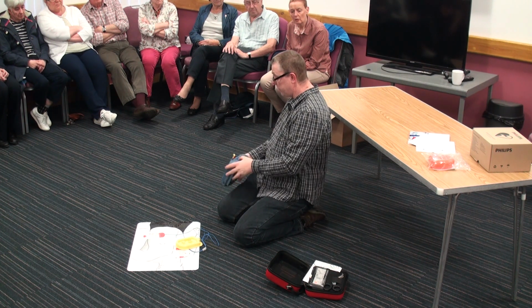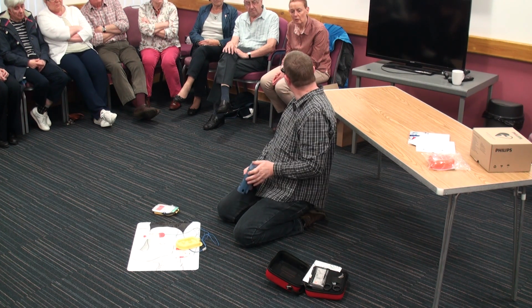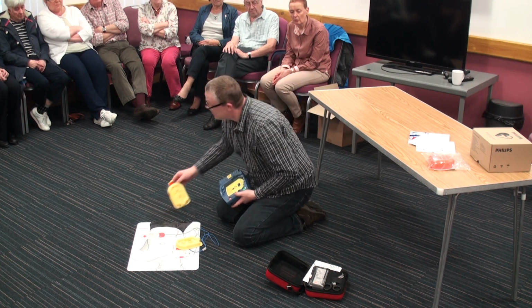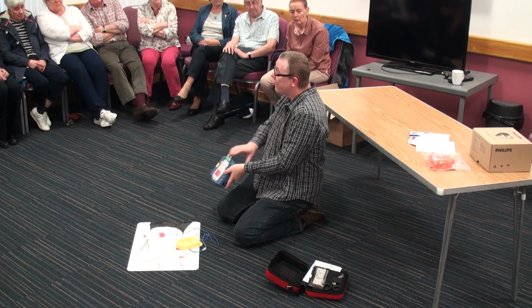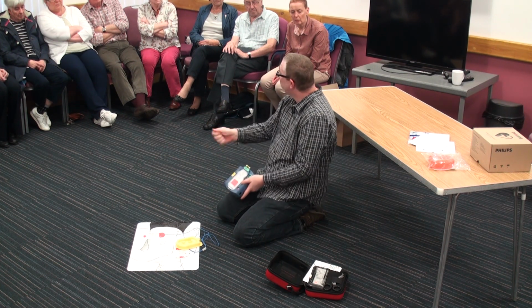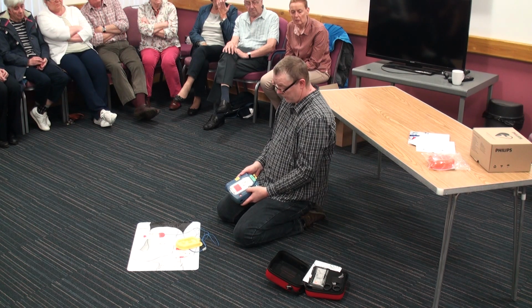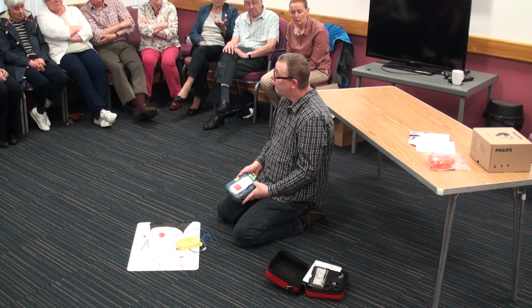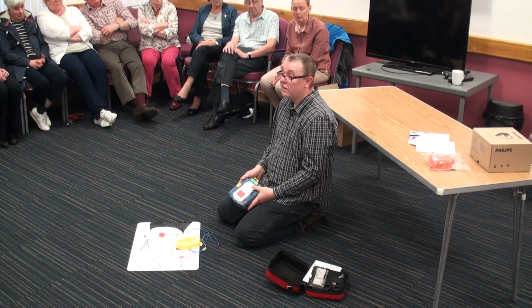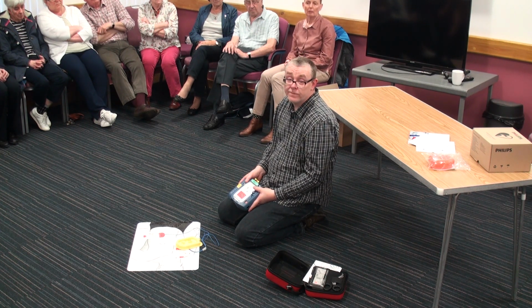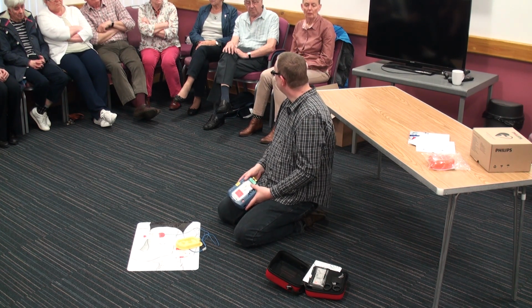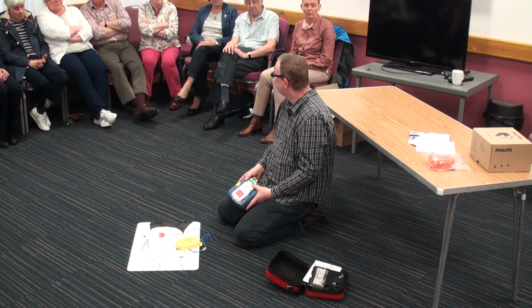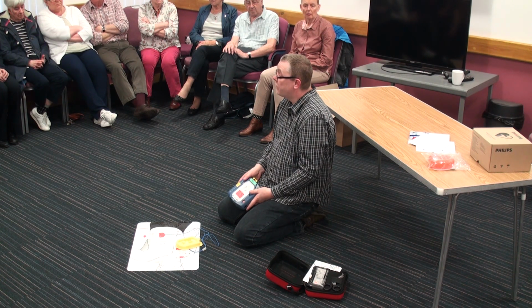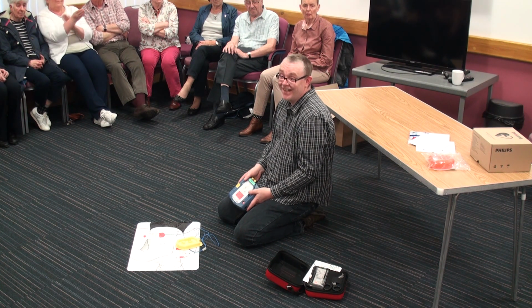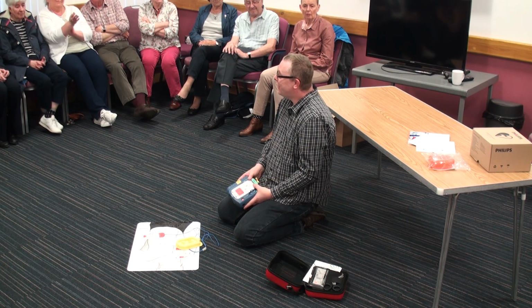Press the flashing blue button to insert the pads cartridge. I grab the child pads, set them in at the bottom, click them in at the top, pull the handle, and the machine goes straight into action. So that's how we change the pads. You have to change the pads once you've used them. You can only use them once. They're single patient use. Once you take them off a man's chest, don't use them on anybody else.